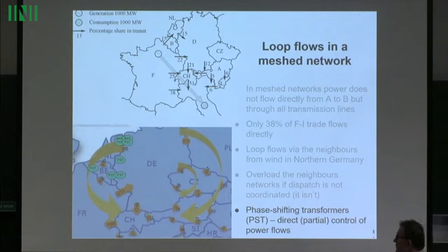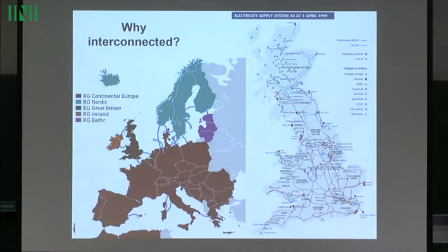One of the problems is that power has to flow somewhere. If you have phase shifting transformers closely located, they have to be coordinated, because one will push power to the left, the other push power to the right, and you can't have both. So there are a lot of problems with that, but there is something to it. As I said, in the afternoon I'll tell you more.